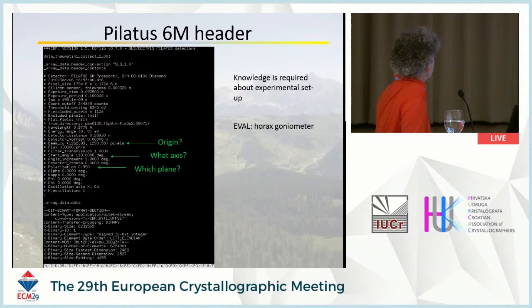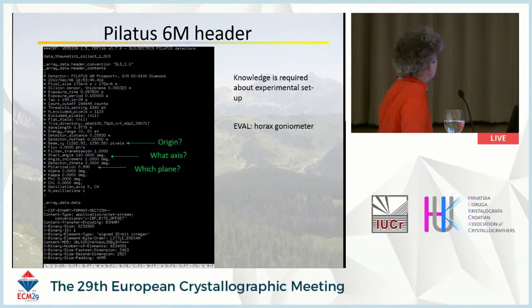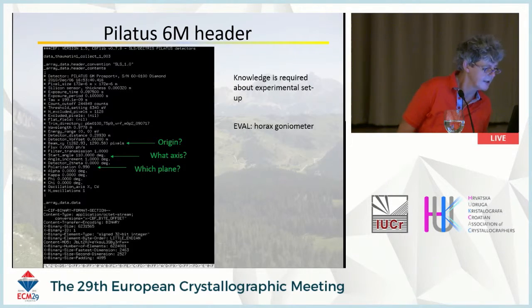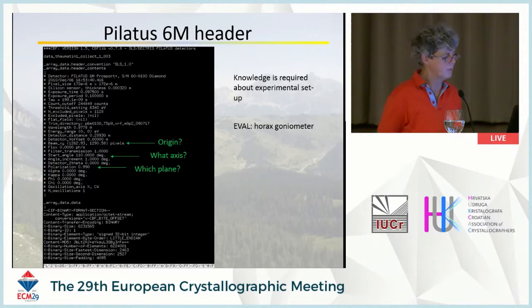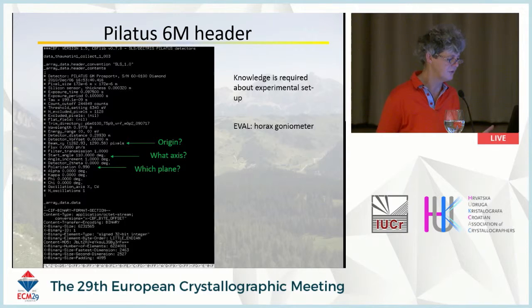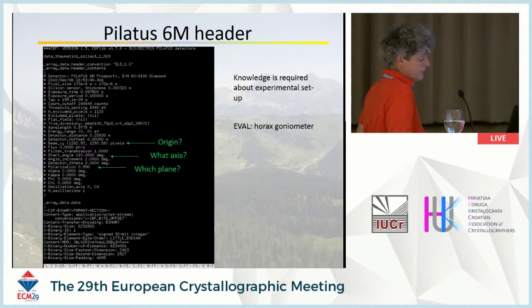This is a Pilatus 6M header. Pilatus uses a mini-CBF format — simply an ASCII header ignoring all the possibilities of imgCIF. It gives beam xy in pixel coordinates but it's not clear where the origin is. There is a starting angle — 110 degrees — but it's not stated which axis it refers to. There is polarization listed but not which plane, and the goniometer type is inferred by EVAL to be a horizontal-axis goniometer, which is normally the case at synchrotrons.